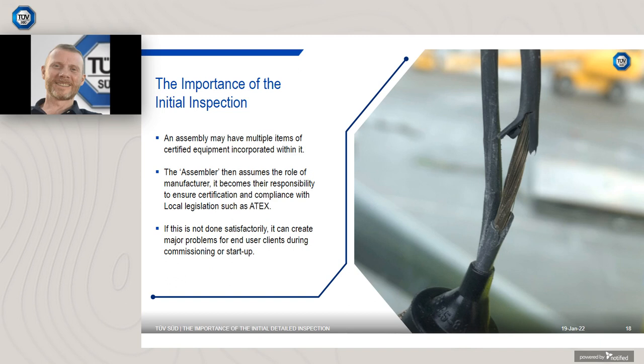Carrying out detailed inspections at subcontractor or fabricator facilities can unearth many costly or potentially dangerous issues with poor installations. If it is not done satisfactorily, it can create major problems for end user clients during commissioning or startup. Delays in project startup or commissioning over compliance issues can be costly and involved. The installation in the photograph was picked up in a detailed inspection at a fabricator yard prior to shipping to end user client site. Repair at site would have been time consuming and costly.